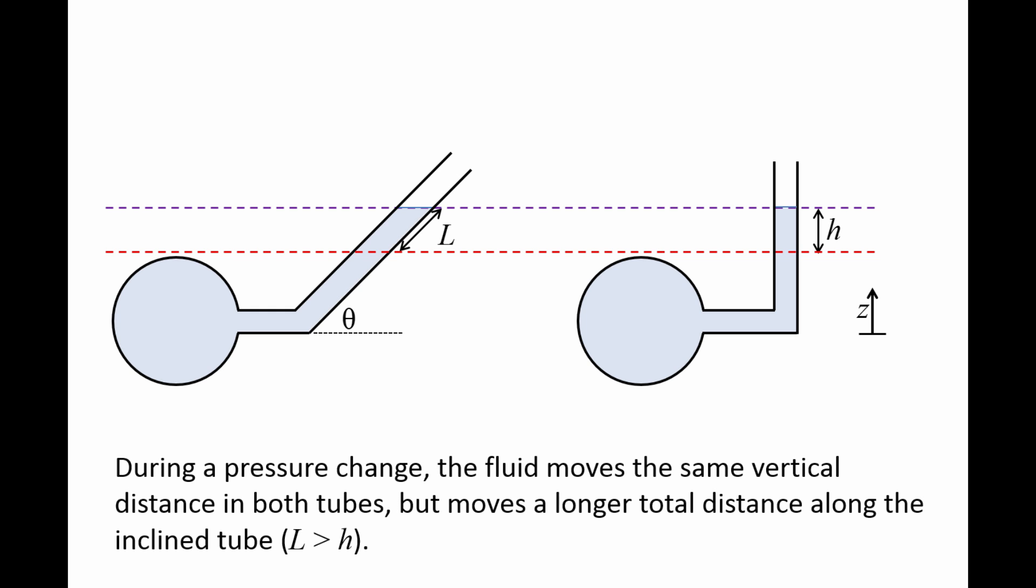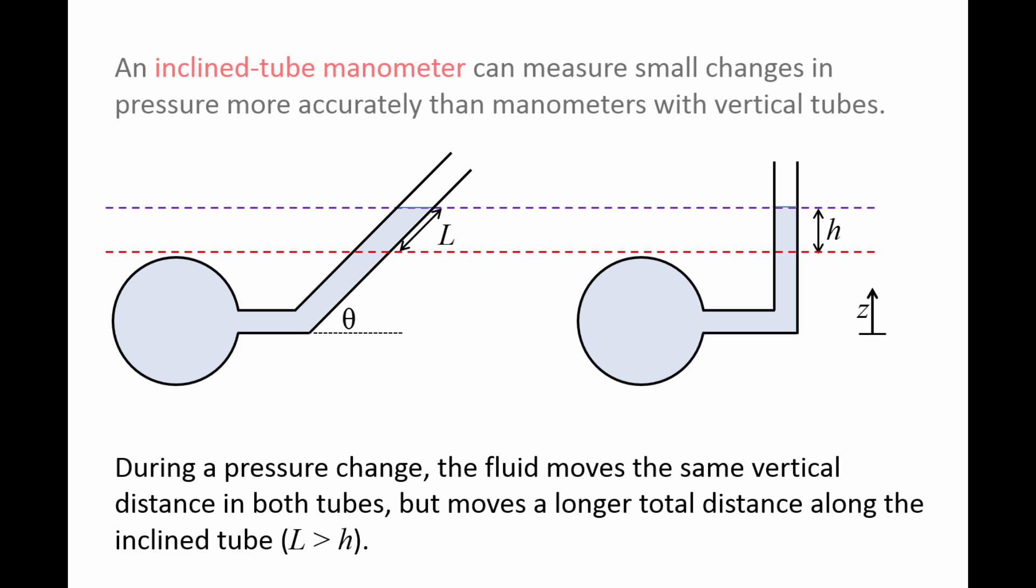So if the fluid level were initially at the red dashed line and an increase in pressure moved the fluid level to the purple line, notice that the distance L is greater than the distance H. So inclined tube manometers can measure small changes in pressure more accurately than manometers that use vertical tubes.